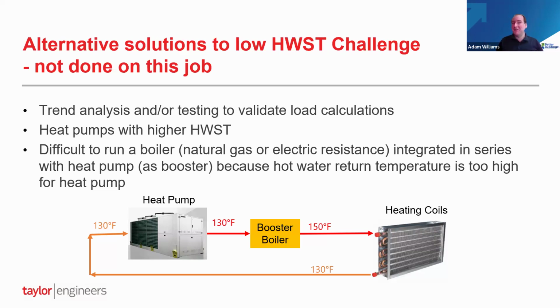The other thing that we have seen and learned some lessons on is some people say, well, if you're concerned about providing 130 hot water, why don't you add an electric or a gas booster boiler in series with the heat pump and heat it up to 150 degrees and send that to your coils? But the problem is, if you're not getting the right delta T across your coils, the hot water return temperature can come back so high that your heat pumps can't really do anything with it.